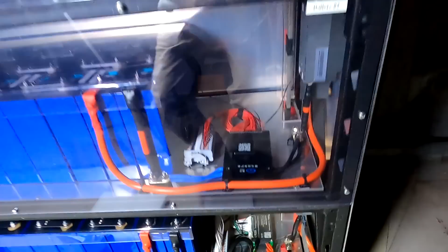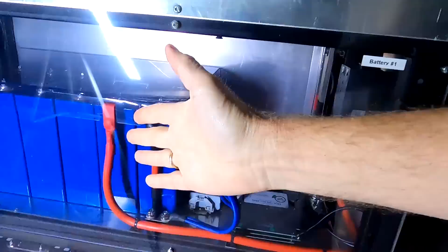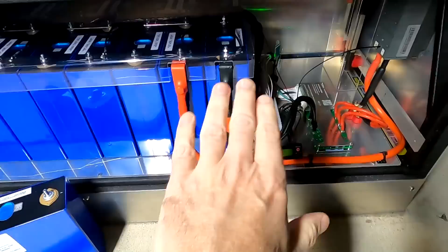Because we are going to work on this battery, I have to shut down this battery bank altogether. That's what we're going to do right now. Let me just turn this one off. The Multiplus is still warming our water because it's now running from the top and middle shelf battery, but not the bottom one anymore. This one is completely shut off. That's why we have positive and negative on these circuit breakers. From the main bus bar system up there, completely isolated. Positive, negative, completely turned off.